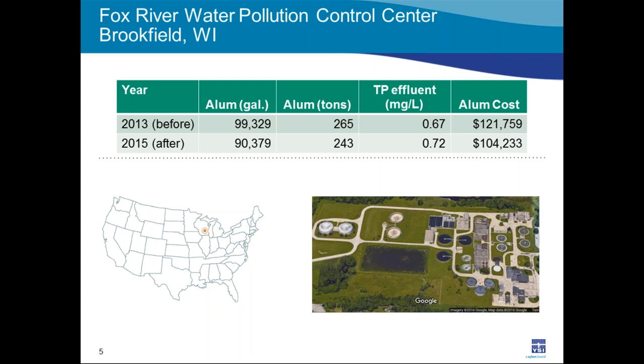The data shown are before and after installation of the P700 phosphate analyzer and its incorporation into the chemical control system. In 2013, the year before the analyzer was installed, alum usage was around 100,000 gallons to produce effluent TP of around 0.7 mg/L at a cost of about $122,000. In 2015, the first full year after installation, alum usage was reduced by 10%, still producing similar effluent quality around 0.7 mg/L, but at a much lower cost of around $104,000.